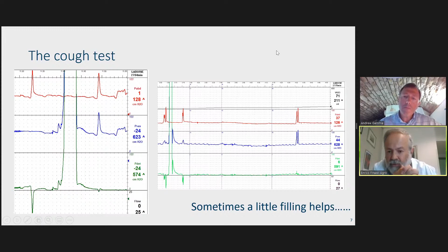Okay, good, thank you. The next thing that can happen during a test is that you get a pressure descending. We've actually mentioned this in passing already. On this trace, you can see that it is starting at 0. So we've already failed one of the quality tests, because the pressure inside our patient at the symphysis pubis is never 0. We're related to atmospheric pressure. So they must have set the 0 inside the bladder, whatever the starting pressure was. And as we've explained, our standard is to make 0 the outside pressure and then register the pressures inside the body with respect to that.